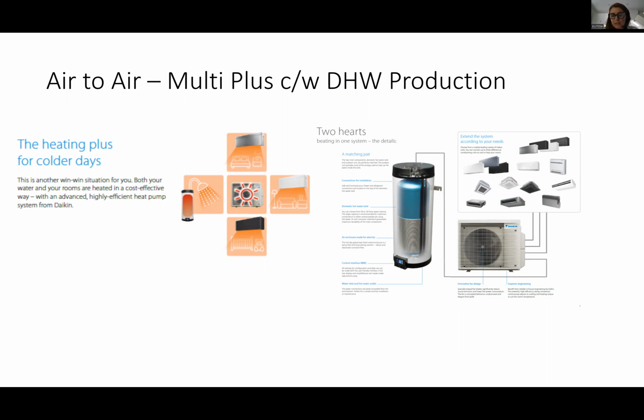So just this year, Daikin brought out what we call the Multi Plus. And this is a domestic hot water cylinder which is connected to the outdoor unit. So now you have an air-to-air system that gives a complete solution for heating, cooling, and hot water. And it's getting the full renewable contribution for the domestic hot water as well as the heating and cooling. So this is a really, really nice solution.